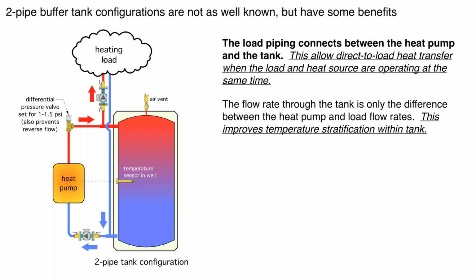Now, that can be a problem. Okay, I'll give you a scenario. Let's say the heat pump is operating at 12 gallons per minute, and let's say the load is taking 12 gallons per minute. All right, so what's happening is all this flow is going up to the load, it's coming back, and it's going back to the heat pump. So there's our circuit right there. And under those conditions, you have zero flow going through the buffer tank. Well, if those conditions persist for a long time, there's kind of no point in having the buffer tank. It's like having a battery and you're not charging the battery at all.